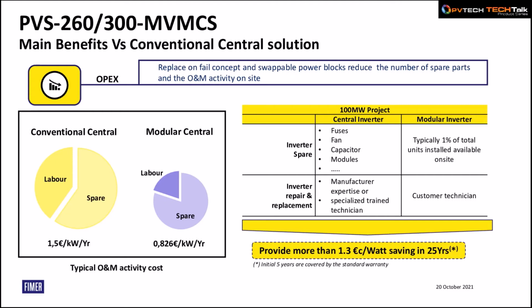So typically just 1% of the total units that are installed are available on site in order to quickly tackle any single point of failure. Inverter repair and replacement is also a relatively trivial task with modular inverters. You can use the customer technicians, unlike central inverters, which normally require the expertise of a manufacturer or a specialized trained technician. Calculating the impact over the service life of the system, we are offering 1.3 euro cents per watt saving in 25 years. And this is the main improvement.